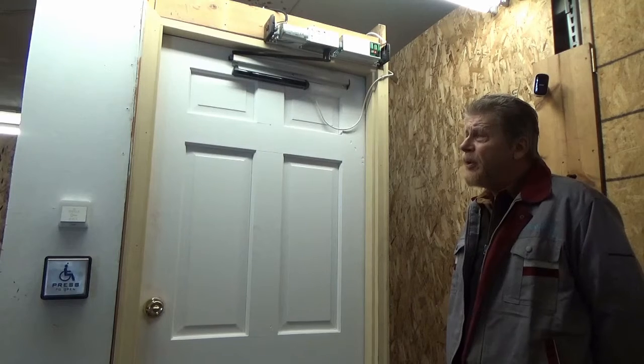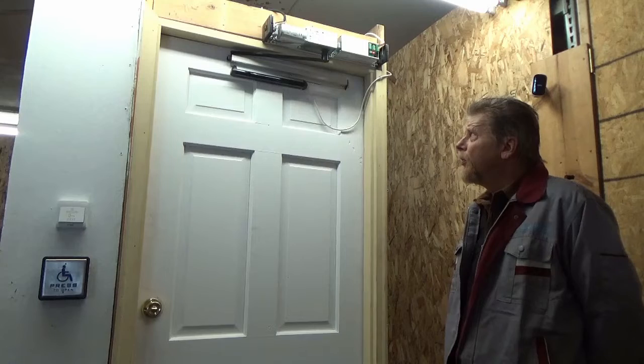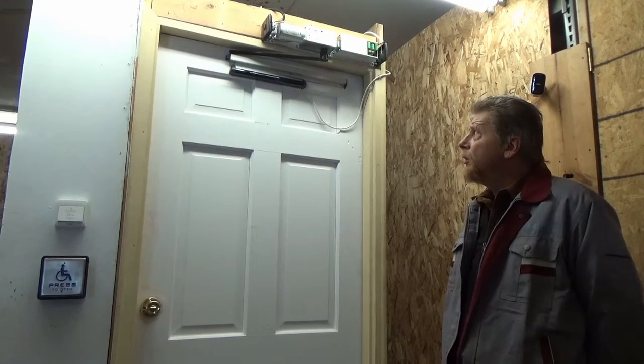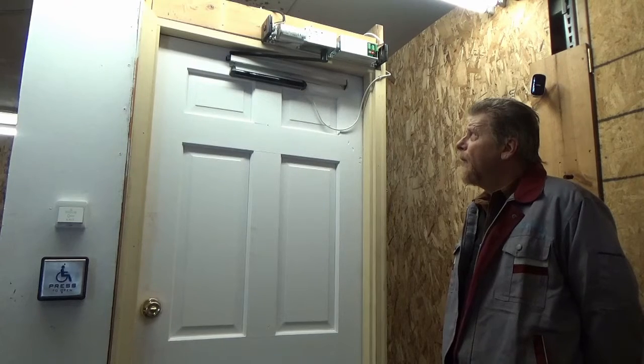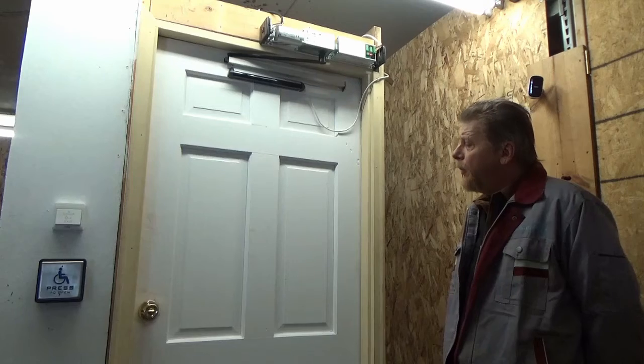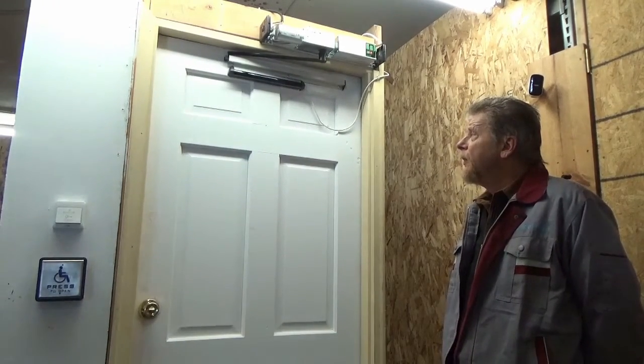It will and it can open the door, but the primary purpose is as a safety beam sensor, and it works well in that capacity. I've mounted mine high and center. Motion sensors are a bit of a weird concept — if they see movement they'll stop, but in this case it's so high up it can't see the ground, so in effect it does not know it's moving.